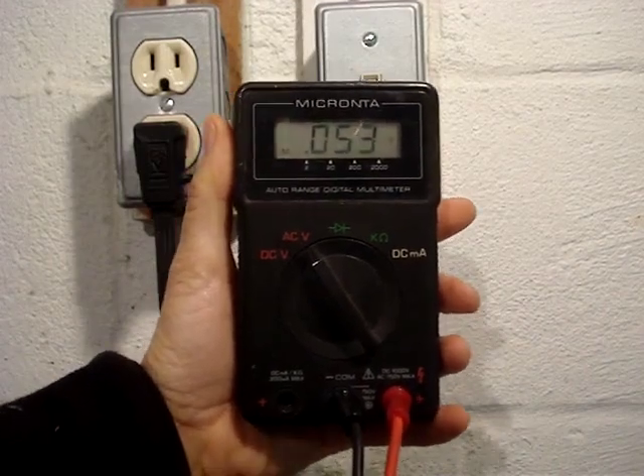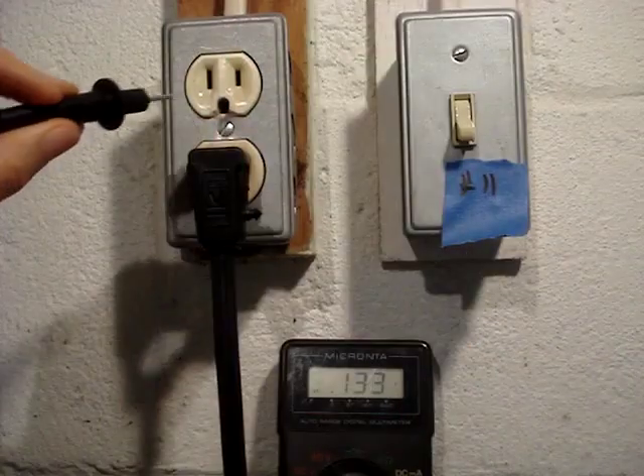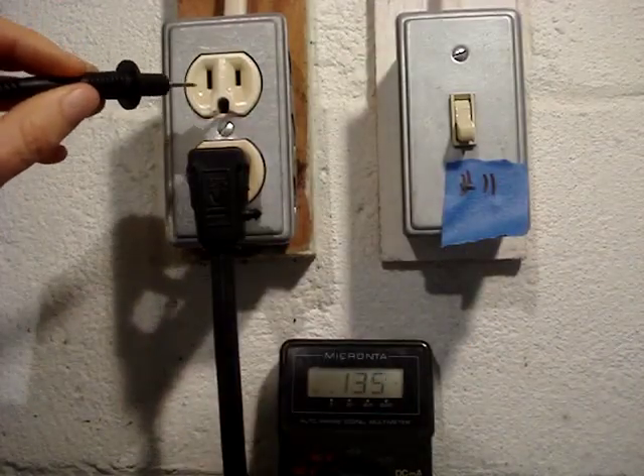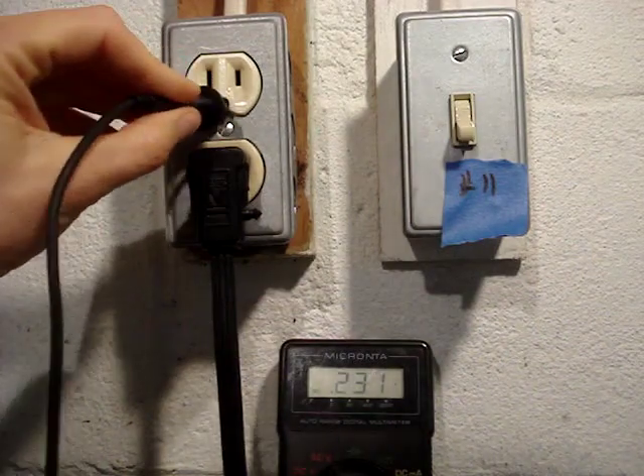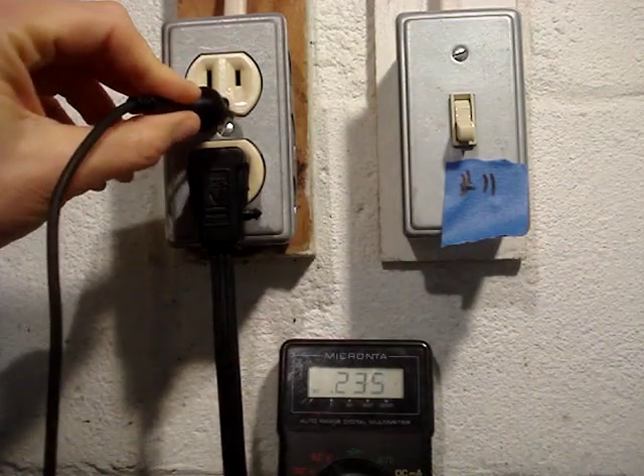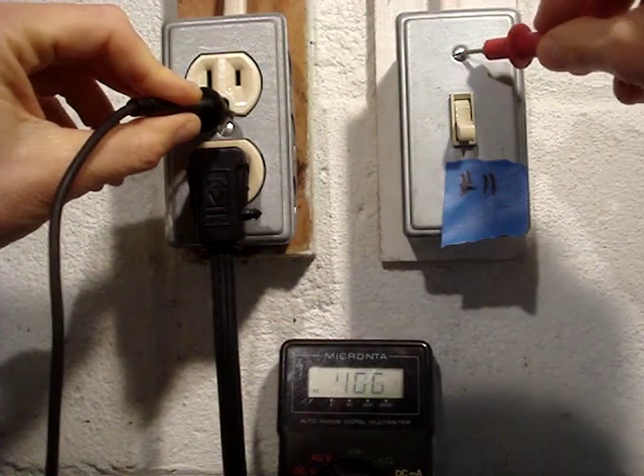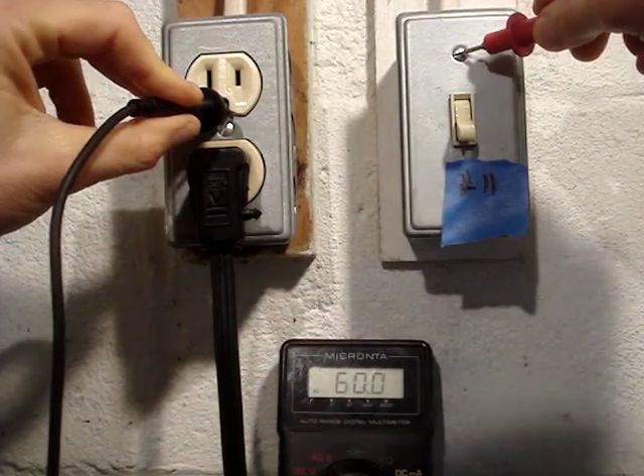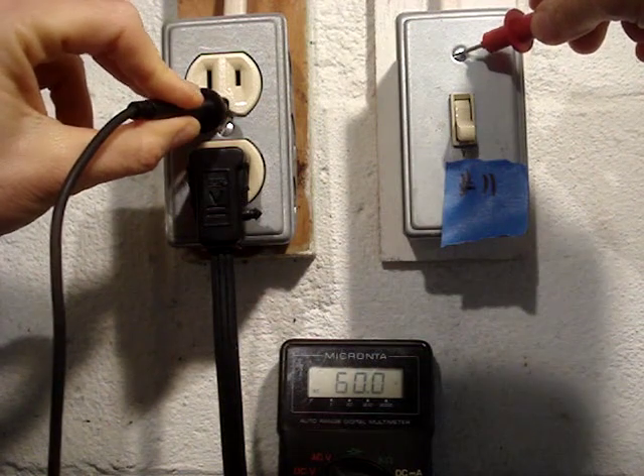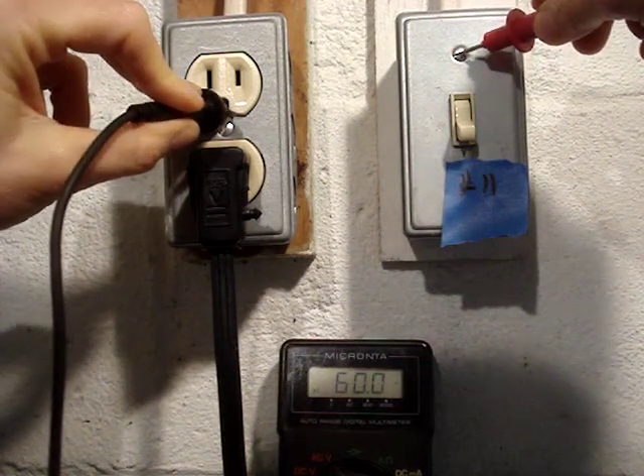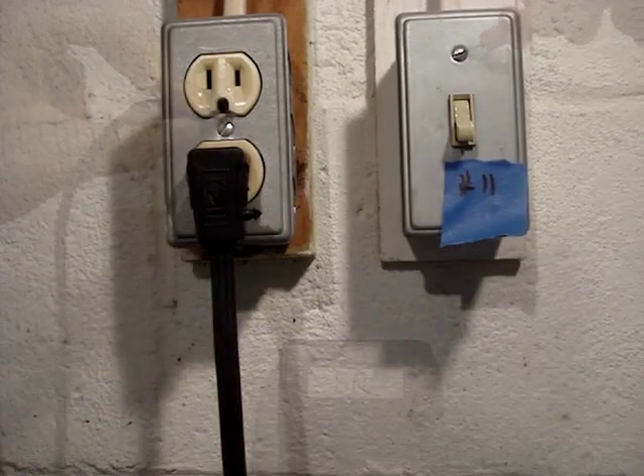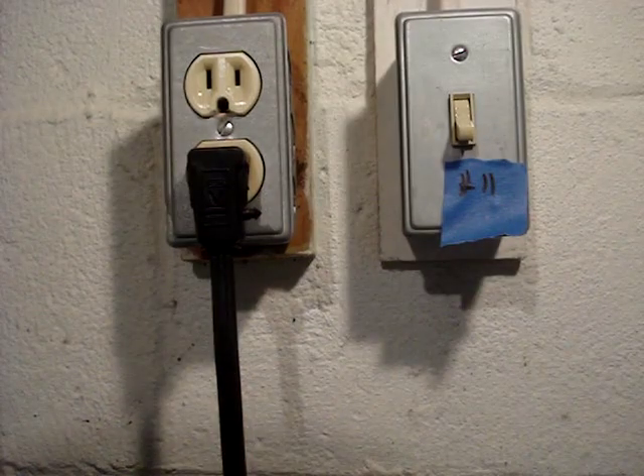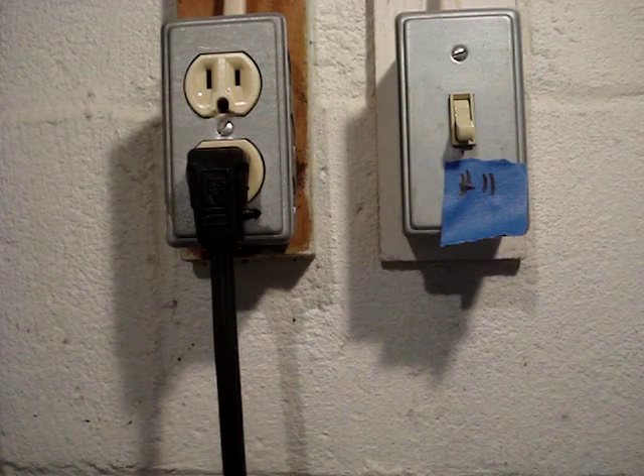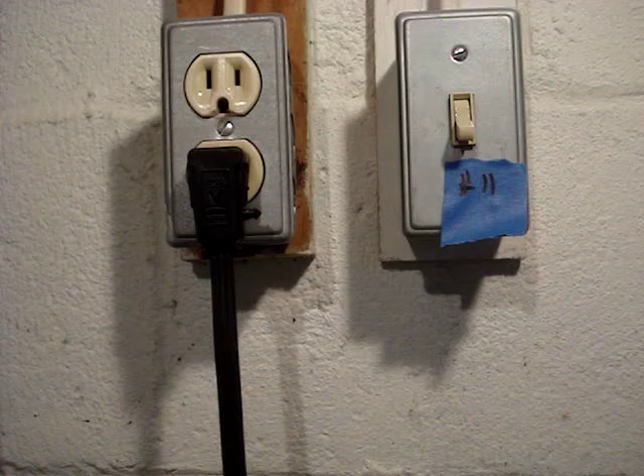I've set my multimeter to read for AC volts. I'll place one probe in another known good ground, in the ground of this other circuit, and this probe onto the metal box of the switch, and I read 60 volts AC. That tells me that the ground wire, which is the bare one, or sometimes it's green, and the hot wire, which is the black one, are shorted together someplace.